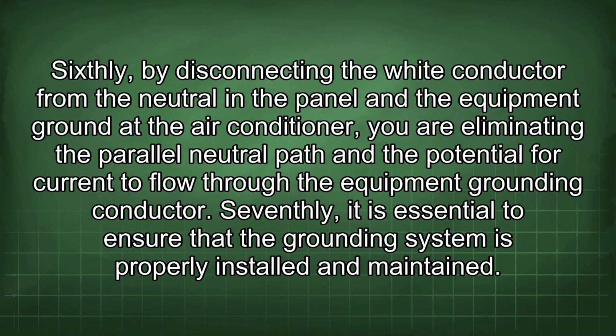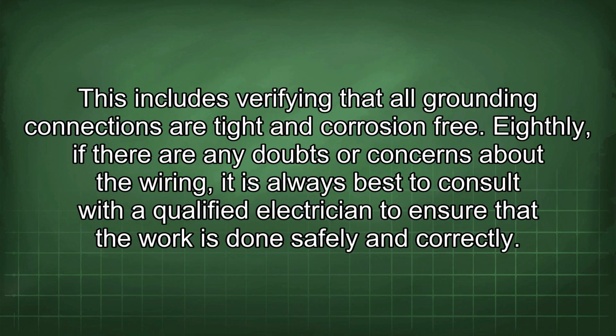Sixthly, by disconnecting the white conductor from the neutral in the panel and the equipment ground at the air conditioner, you are eliminating the parallel neutral path and the potential for current to flow through the equipment grounding conductor. Seventhly, it is essential to ensure that the grounding system is properly installed and maintained. This includes verifying that all grounding connections are tight and corrosion-free.